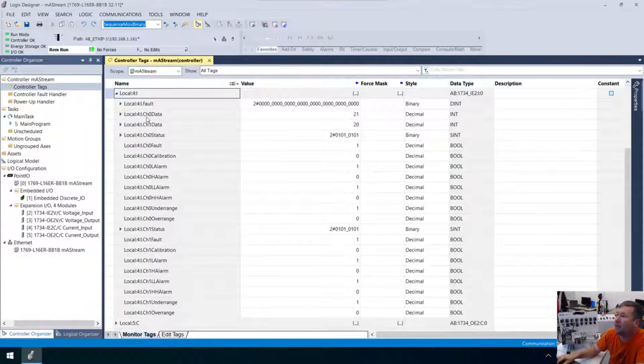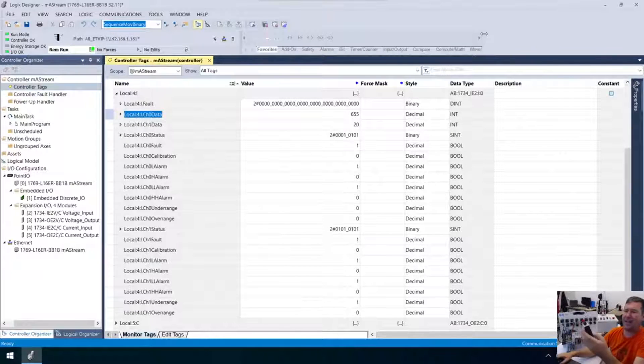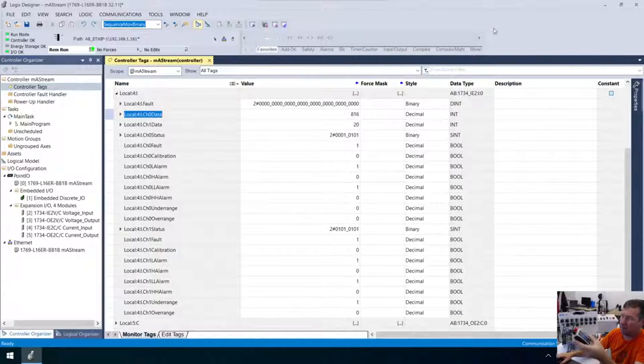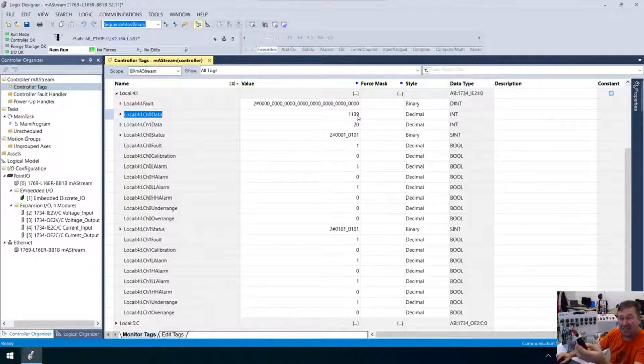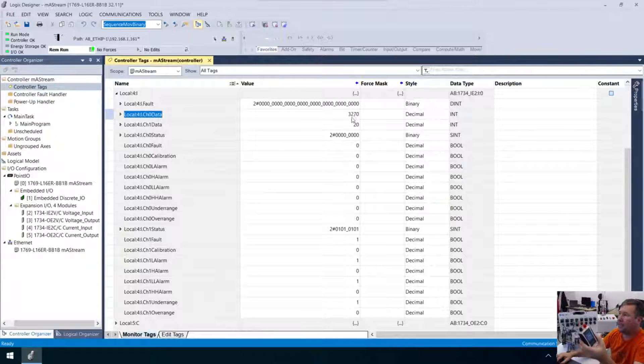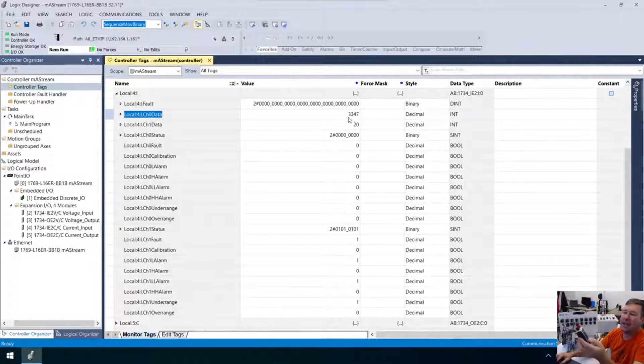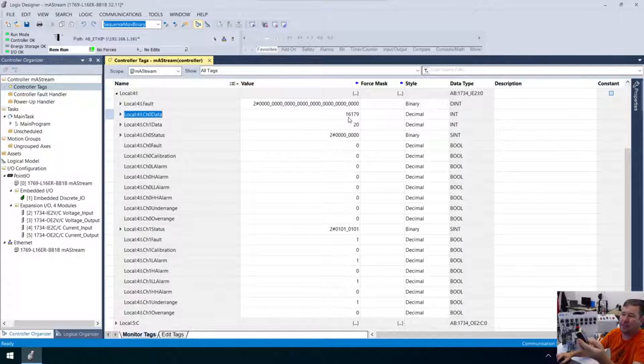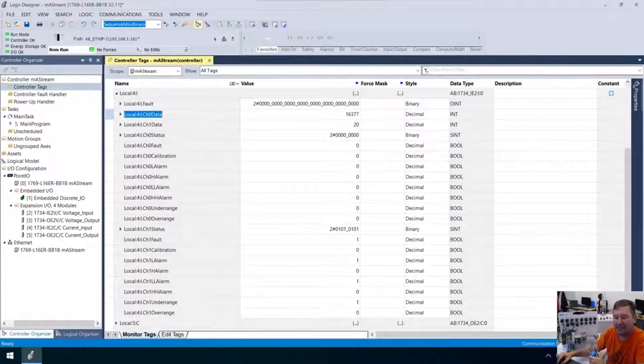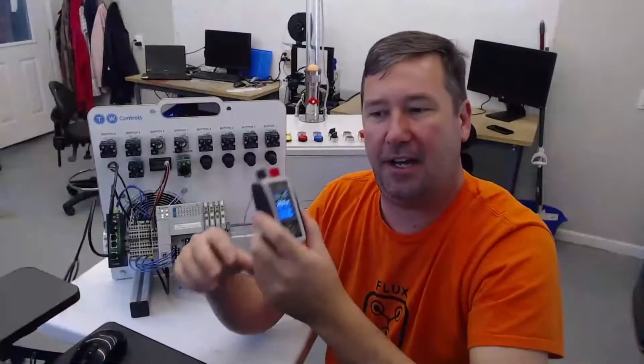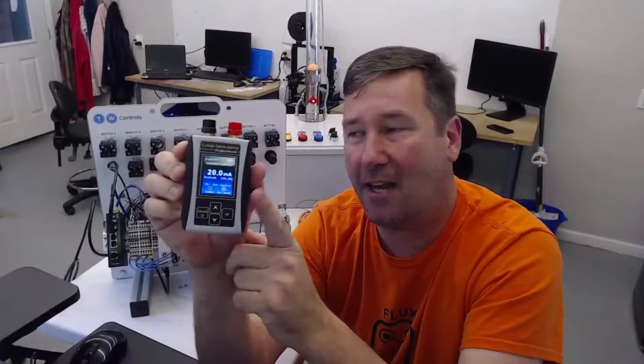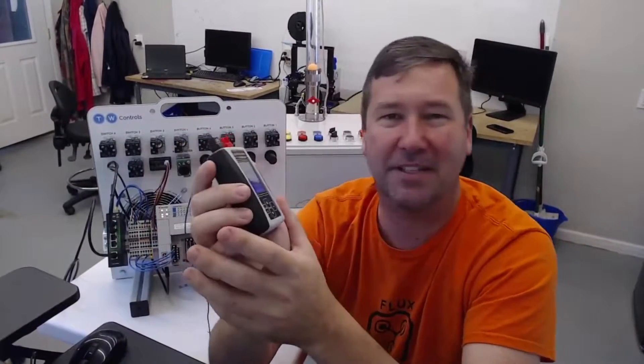Input. And we are looking at this channel data right here. See, all right, I've got it at 1 milliamp right now. And we're seeing a crazy value here, 816. But this is a 4 to 20 milliamp signal. So let's bring it up to 4. Whoops, went too far. And at 4 milliamps, it's showing right at 3270. And if we go up to 20 milliamps, then we are showing 16378. And so these are the rough values of this. So we're at 20 milliamps now. And yeah, we're seeing 16, what, 16378.